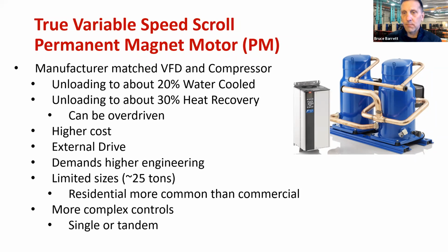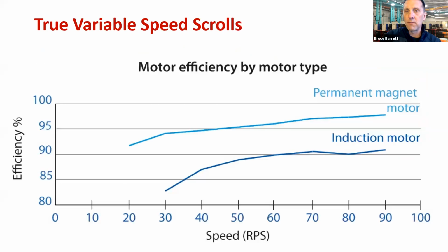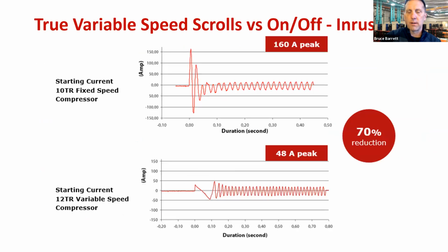They can be single or tandem. You can just put one of those compressors to be your first on, last off. And again, achieve better temperature control on a heat recovery chiller using a true variable speed compressor. There's also some bonuses there. Motor efficiency, out of the box, never worse than 92% motor efficiency versus an on-off compressor. Inrush, you can really lower your electrical wiring costs and improve your inrush on your total system performance.